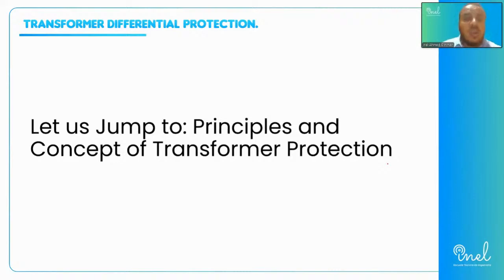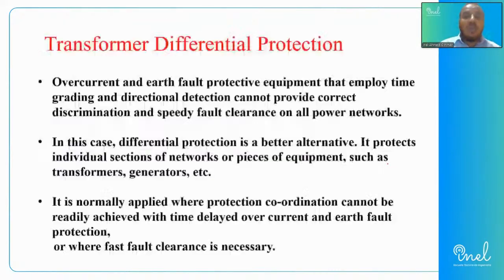Let's jump now to the second title, which is transformer protection, about the differential. The differential protection is a level of protection which can allow a second backup over the overcurrent. We have overcurrent protection, and we have other protection on the transformer, which can be named earth fault. But due to the nature of the transformer, where we have primary current and secondary current with a proportional ratio between them, we need a higher level of protection, which overcurrent may not be suitable for, and such level of protection is differential protection. So differential protection would be like a second layer over overcurrent and earth fault.